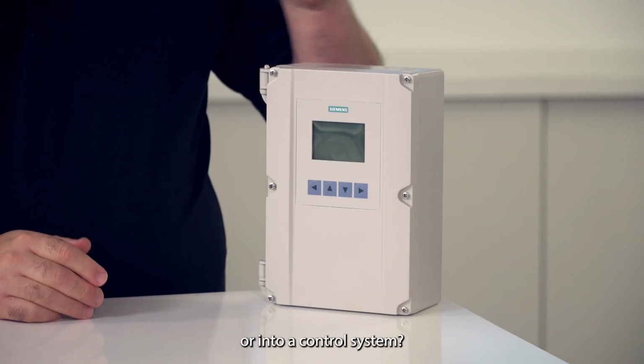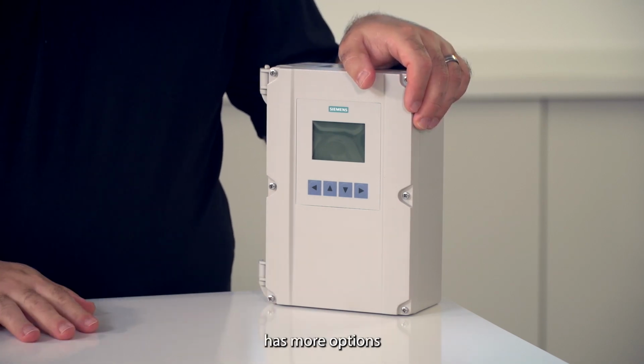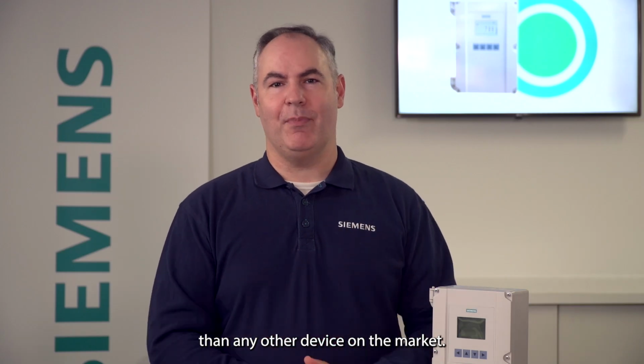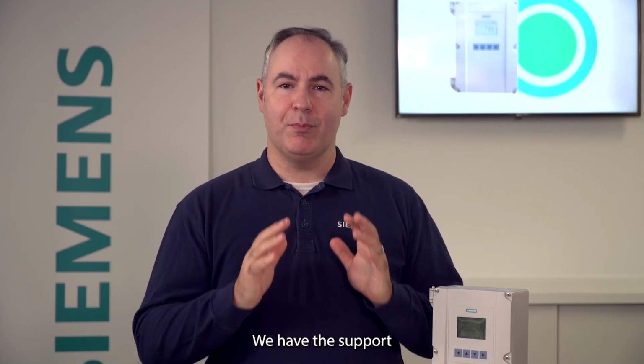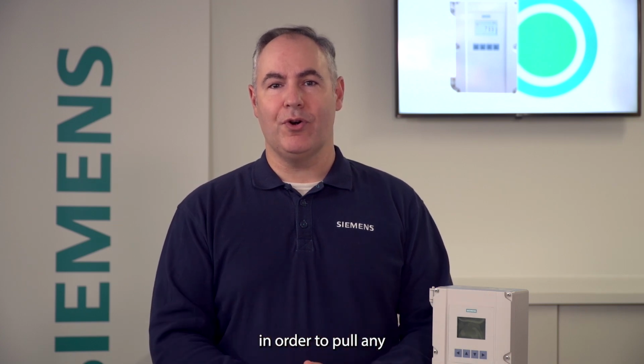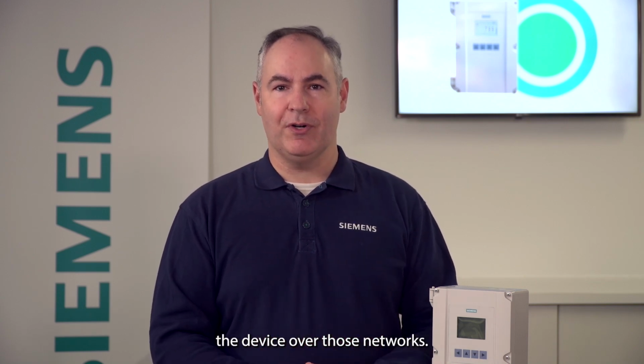Are you looking to integrate your level measurement device onto a field bus or into a control system? SITRANS LT500 has more options than any other device on the market. Let's start with the simple protocols like HART, Modbus RTU, Profibus PA, and Profibus DP. We have the support files and documentation in order to pull any and all of the data out of your SITRANS LT500 and integrate the device over those networks.